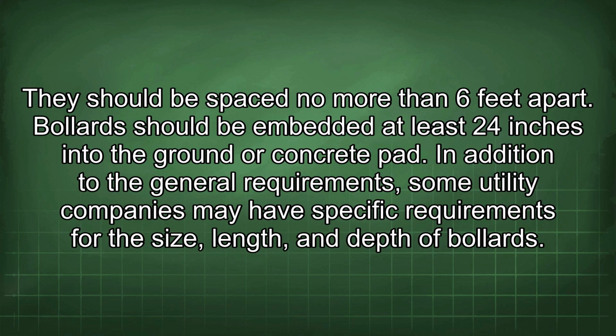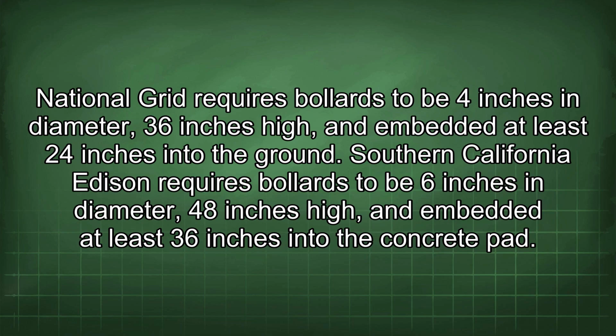In addition to the general requirements, some utility companies may have specific requirements for the size, length, and depth of bollards. National Grid requires bollards to be 4 inches in diameter, 36 inches high, and embedded at least 24 inches into the ground. Southern California Edison requires bollards to be 6 inches in diameter, 48 inches high, and embedded at least 36 inches into the concrete pad.